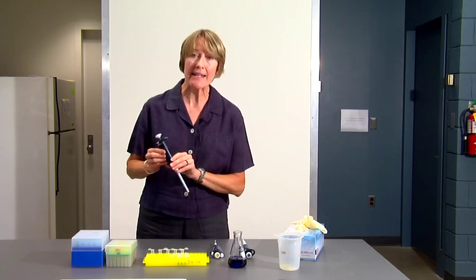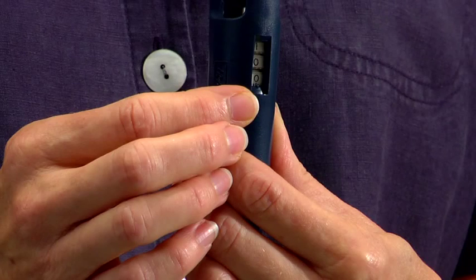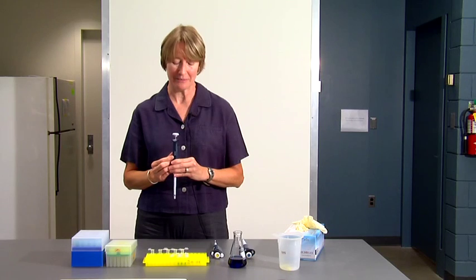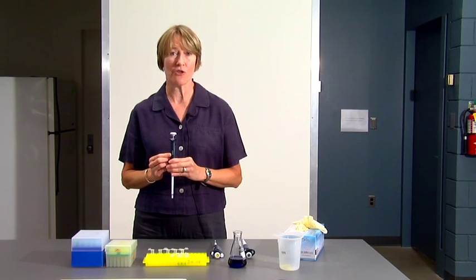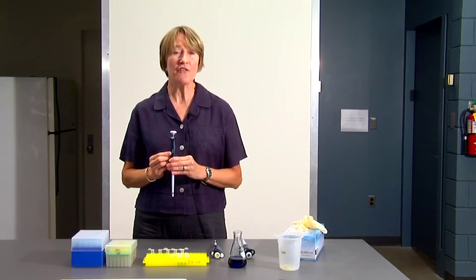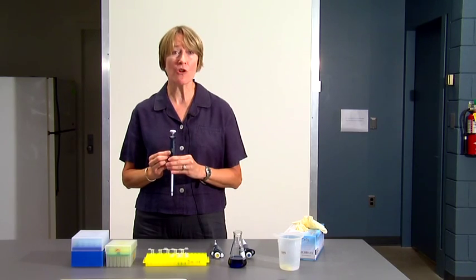On the P200, you have three black numbers on the dial, and essentially what you see is what you get. If the pipetter is set at 100, that will measure 100 microliters. If you wanted 200 microliters, you would set it at 200. 50 microliters would be 050.